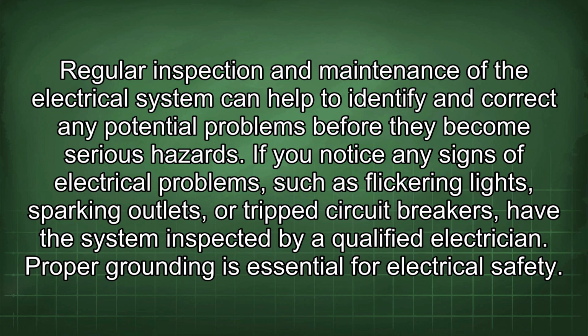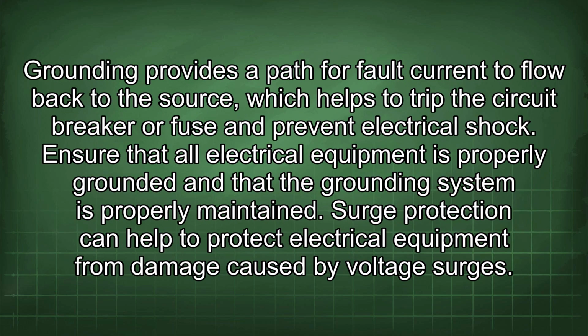Proper grounding is essential for electrical safety. Grounding provides a path for fault current to flow back to the source, which helps to trip the circuit breaker or fuse and prevent electrical shock. Ensure that all electrical equipment is properly grounded and that the grounding system is properly maintained.